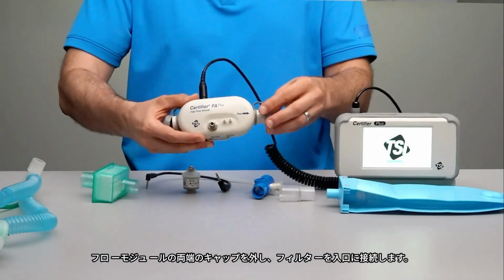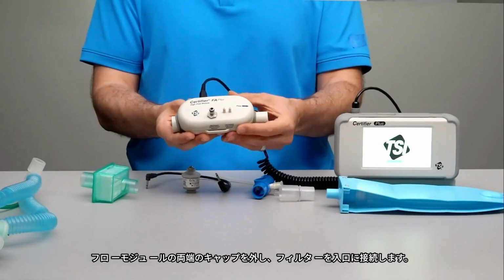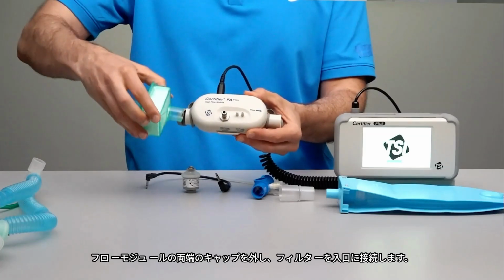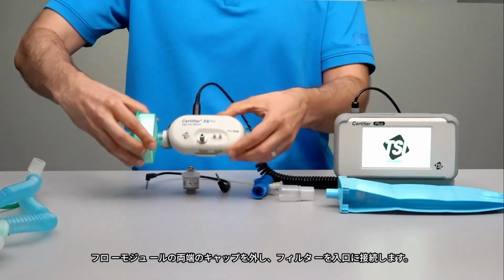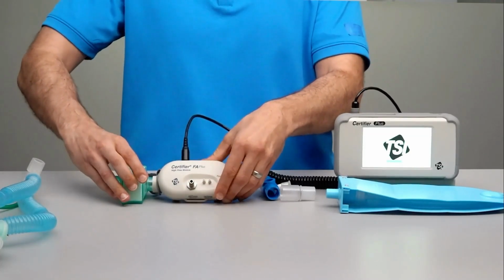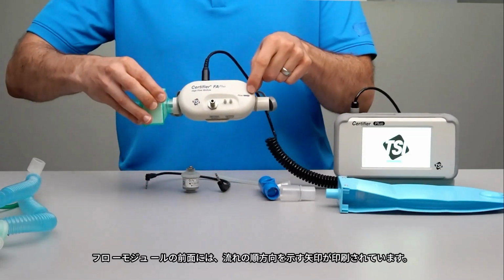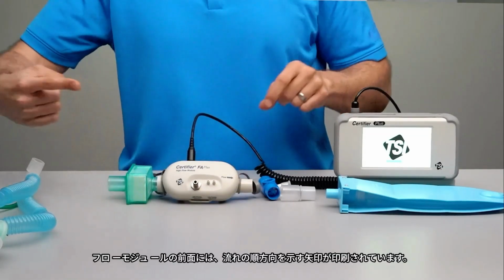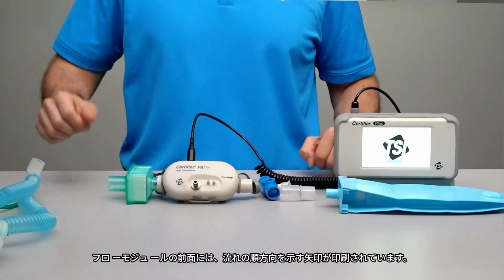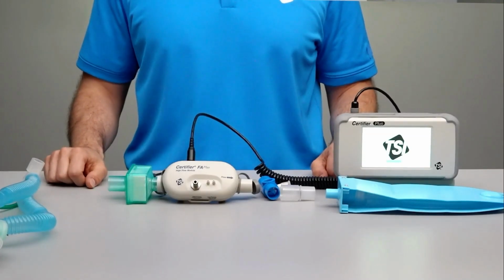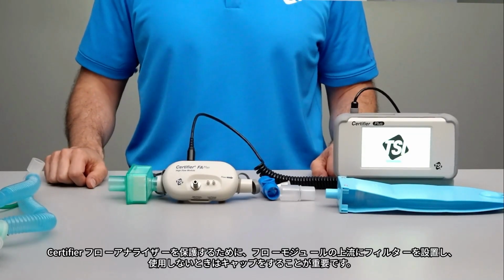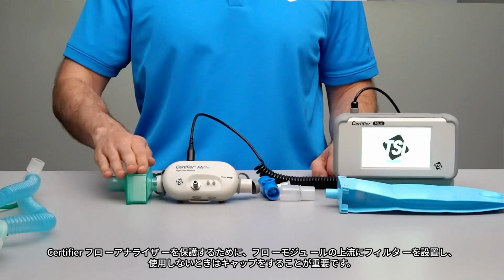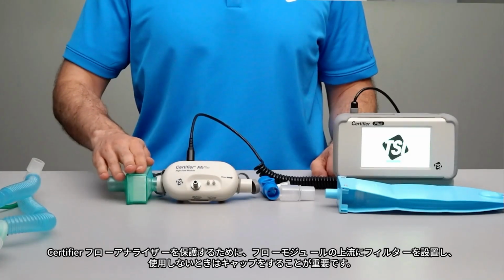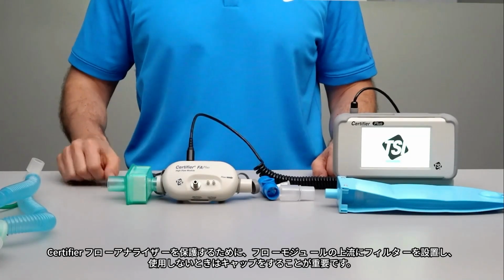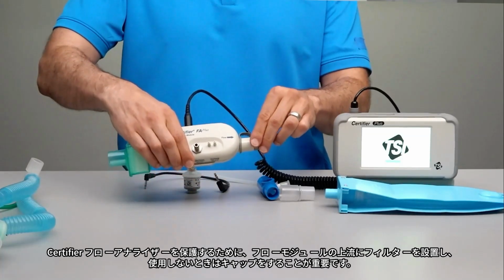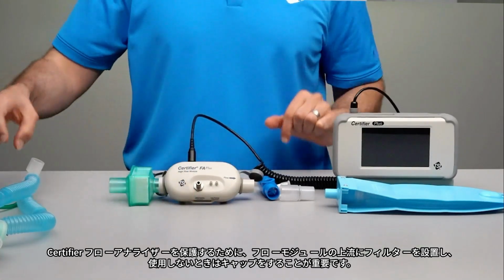Uncap the ends of the flow module and connect the filter to the inlet. There's an arrow printed on the front of the flow module to indicate the forward direction of flow. To protect your Certifier flow analyzer, it's important to always operate with a filter upstream of the flow module and to cap the ends when not in use.